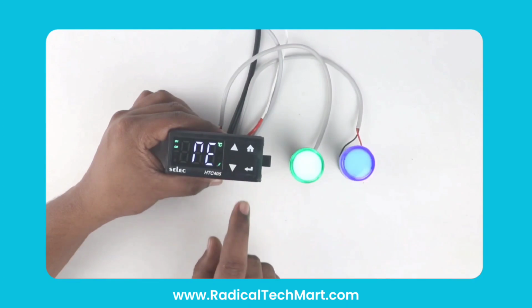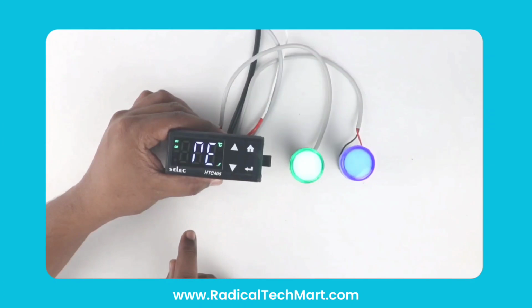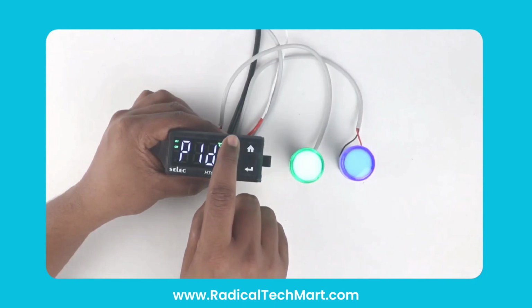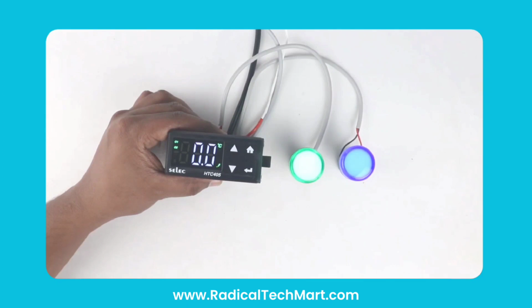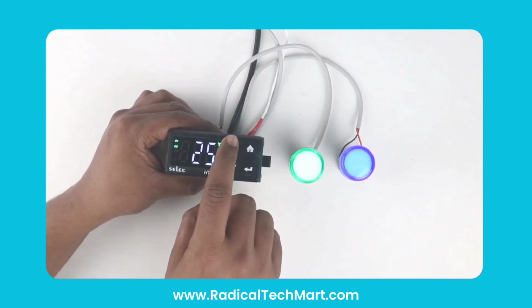Then, select the control logic, ON/OFF or PID. I will choose PID control. Next is temperature display bias. Like humidity, you can adjust this if sensor location causes variation, up to plus or minus 19.9. The anti-reset windup parameter should be kept at default.